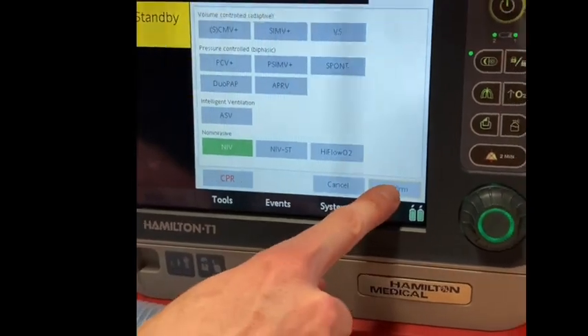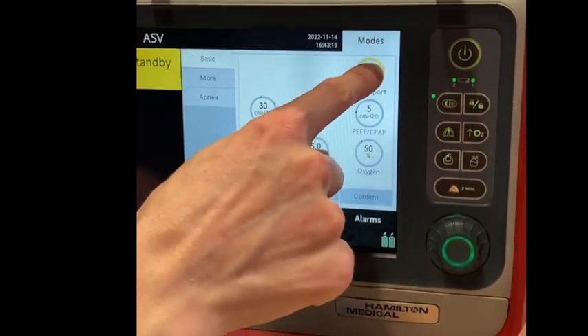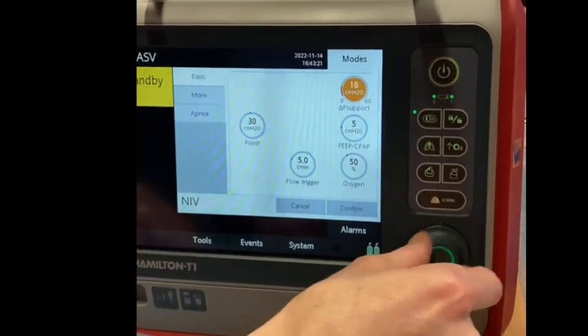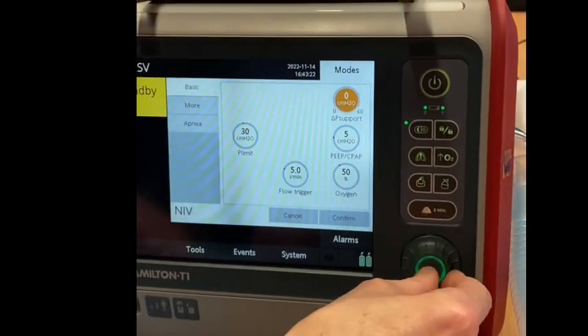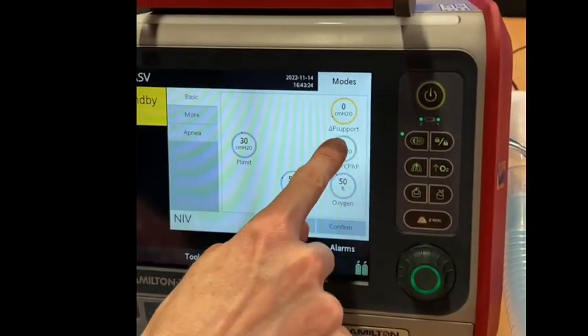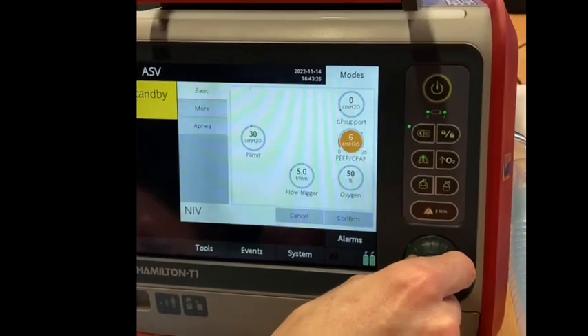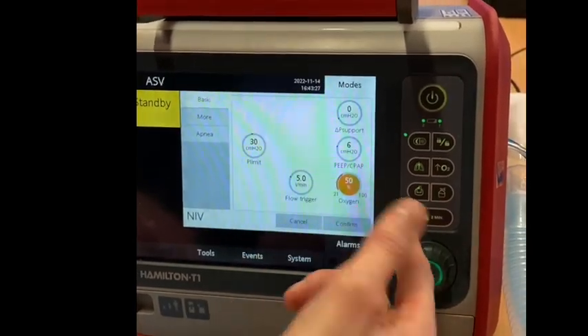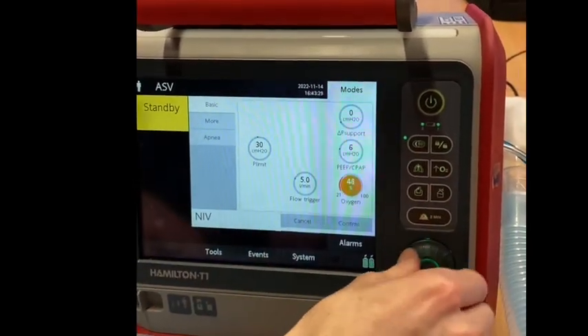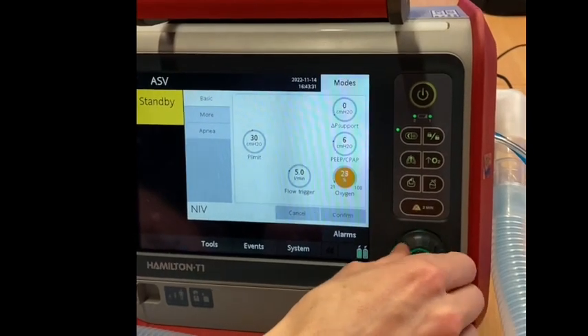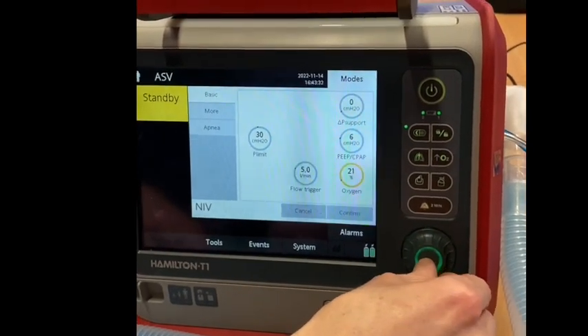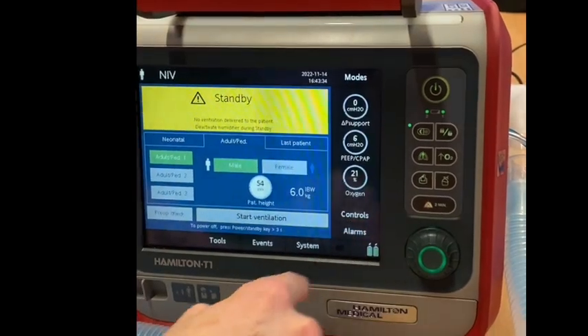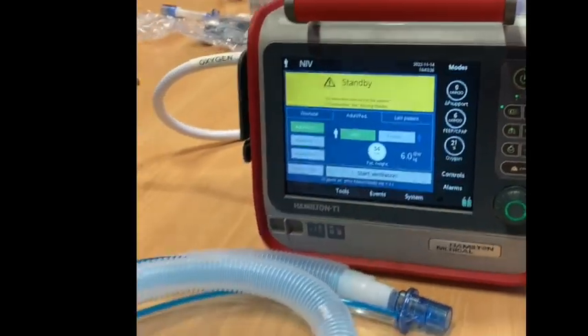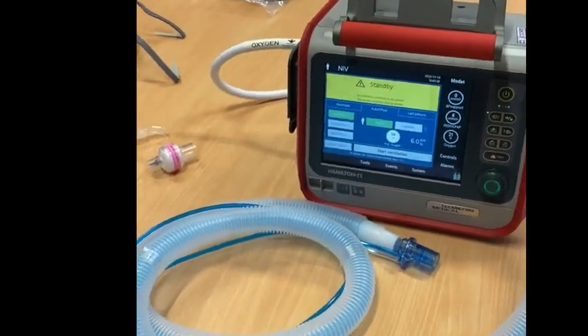For transfer, we typically use CPAP only. To deliver CPAP in this mode, you simply have to remove pressure support, turn it down to 0, and then select the desired CPAP. For tolerance purposes, we often recommend starting at a lower CPAP, 3 to 4 centimeters of water, and then increasing to your final desired PEEP once the child is settled with the mask. Set the FiO2 as required, and then you're ready to commence CPAP.